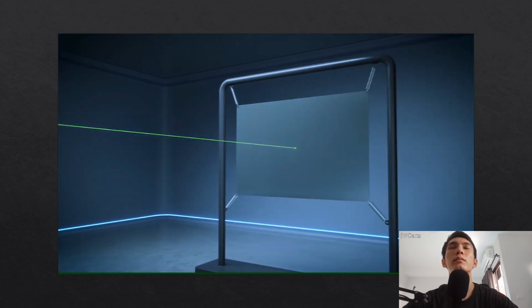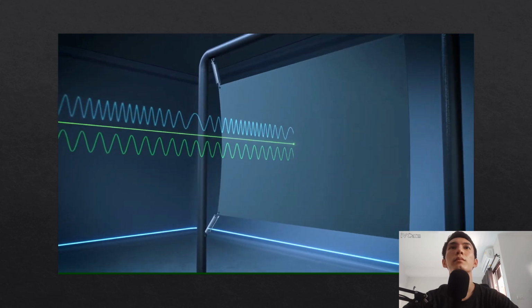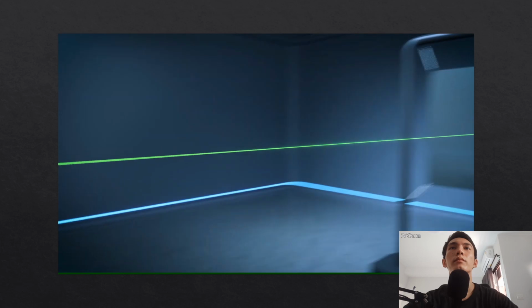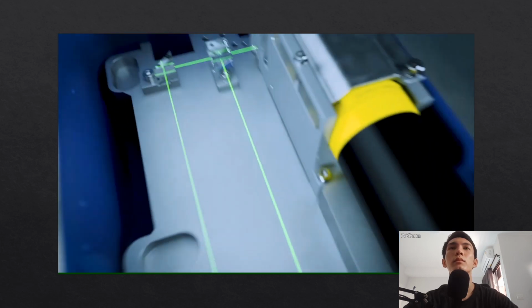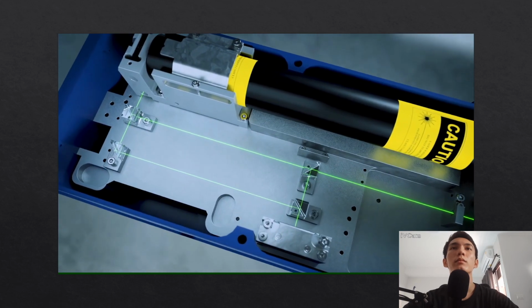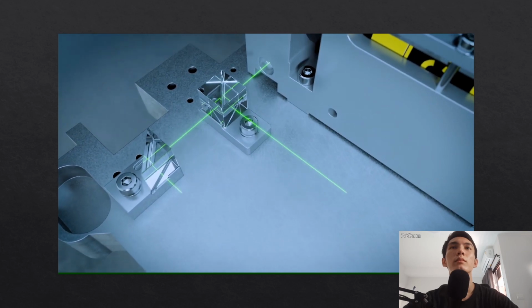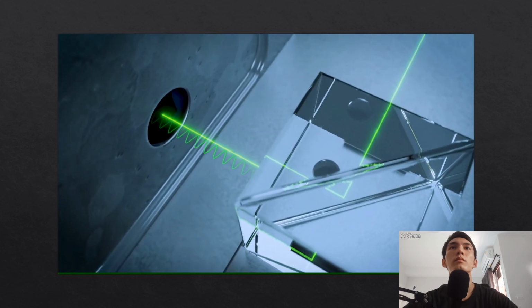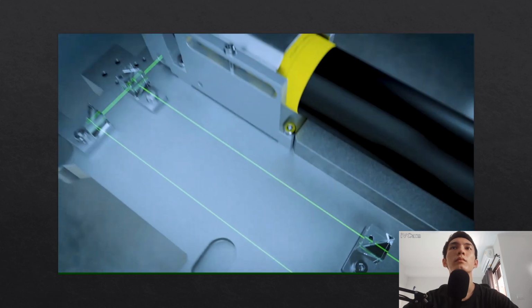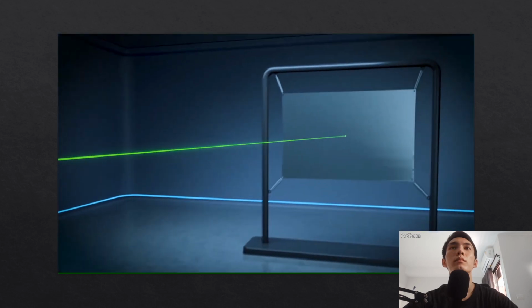Laser vibrometry uses the Doppler effect to measure vibrations. If light is scattered from a moving object, its frequency is changed slightly. Within a Polytec vibrometer, a high-precision interferometer detects the minute frequency shifts of the backscattered laser light. To achieve this, the interferometer splits the light into two parts. The so-called reference beam is pointed directly to the photodetector, while the measurement beam is incident on the test object where the light is scattered by the moving surface.